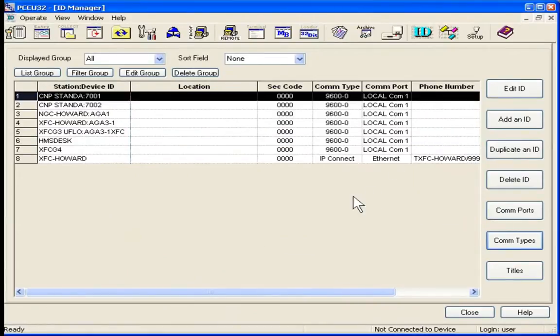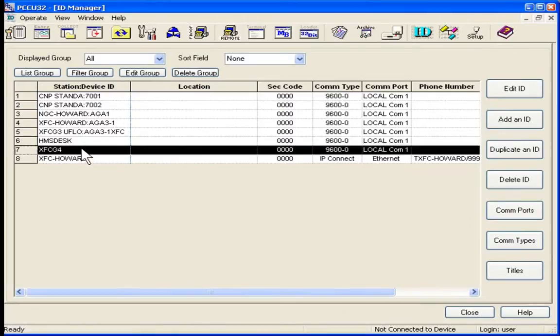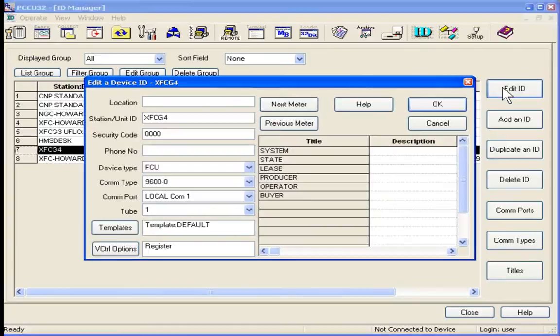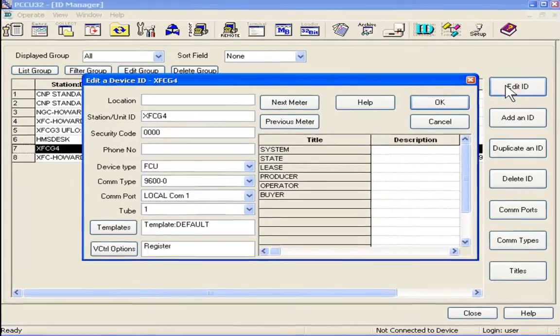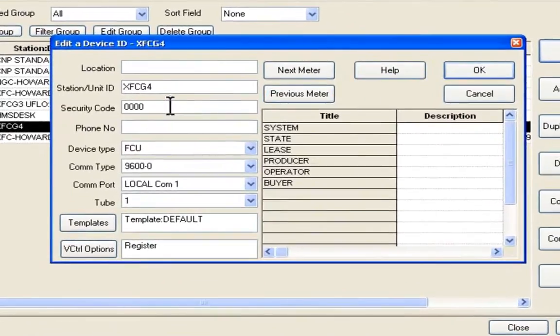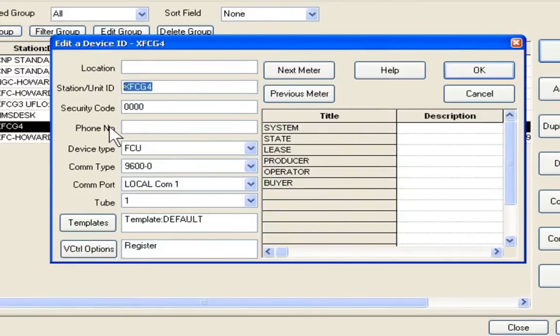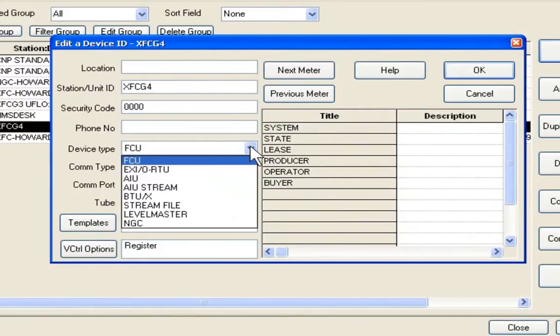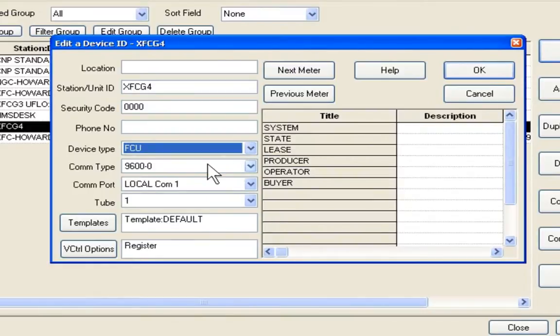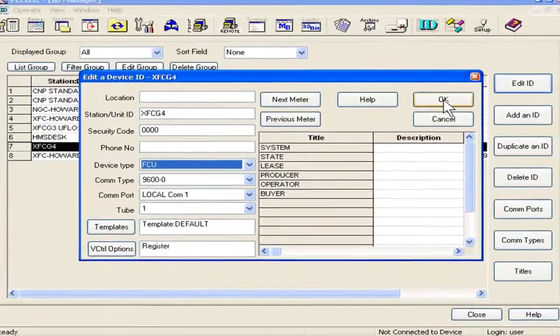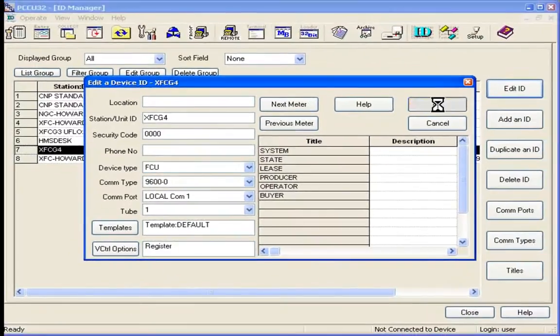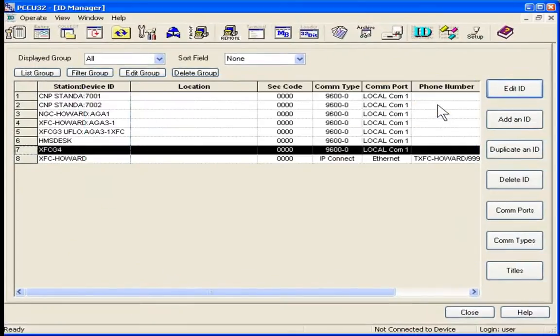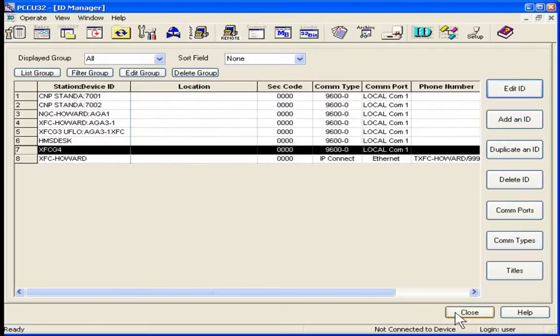Finally, now that we've set up our comm port and comm type, we need to actually set up our G4 device and finalize it in ID manager. So we'll select ID. Go in and edit. Security codes, four zeros. It is a flow computer unit. And here's our comm types and comm ports that we set up previously. Say OK there. Now we've established the ID in the ID manager.